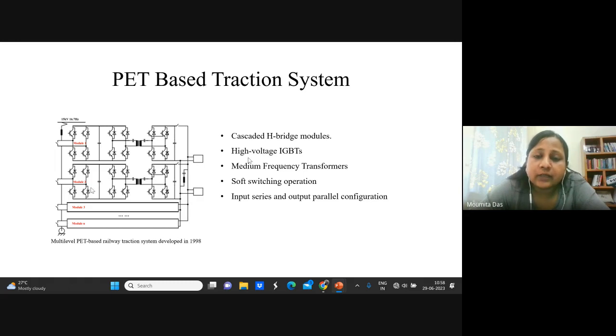So the structure suggests that on the input side, the cascaded H bridge modules are there, and high voltage IGBTs are used, while on the output side parallel configurations are used. Because the input voltage is very high, series combinations are used at the input side, and since the output current requirement is very high, parallel combinations are used at the output side. The advantage of this kind of system is that it has soft switching operation, which reduces the losses in different IGBTs and improves the efficiency of the system.